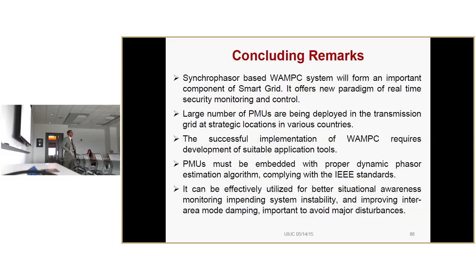Well, synchrophasor-based technology is going to be popular in the electricity grid, at least in the transmission network for the time being. But I'm sure the scope will span to the distribution network, but you have to develop low-cost PMUs, micro PMUs, and so on. I believe there is some work going on in various parts of the US. Because when renewable integration is increasing, maintaining stability becomes very, very challenging. New types of oscillations you will observe. I was sharing my experience with somebody that our southern grid has a lot of wind power. And PMUs started observing a very unusual frequency. And then we simulated, and we found that there is a voltage oscillation always present, of 10 hertz frequency. So you will find new phenomena there. So it will become very challenging.